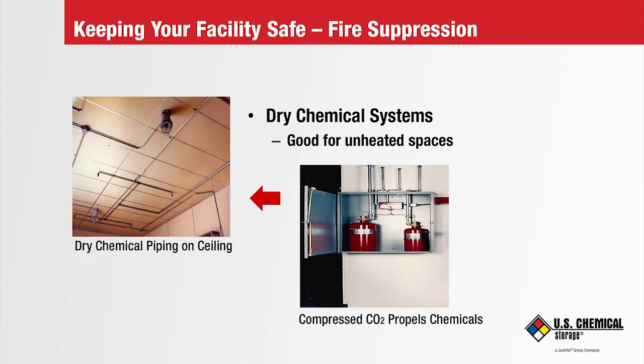The powder mix is contained in a storage tank. This dry chemical, when released, is propelled by compressed CO2. The heads do not come with fusible links, as in the water sprinkler system. Within inches and parallel to the piping, a cable is strung on the ceiling from far within the building, running all the way back to the controls.